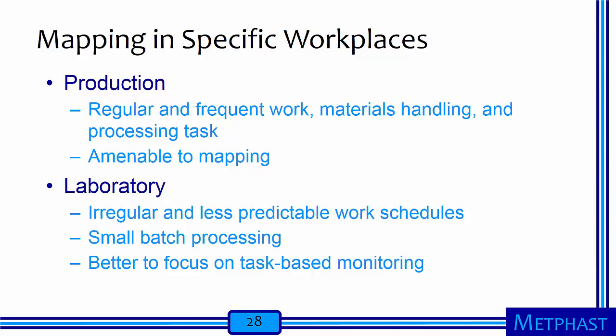Hazard mapping can be extremely useful; however, one must consider its use in specific workplaces. In production facilities with regular and frequent work, materials handling, and processing tasks, one can reasonably expect that concentrations will be temporally stable, and such facilities are amenable to hazard mapping. However, facilities with irregular and less predictable work schedules, like the research laboratory, have small batch processing that leads to high temporal variability in concentrations. Temporal variability introduces substantial uncertainty in hazard mapping, so it is sometimes better to focus on task-based monitoring.